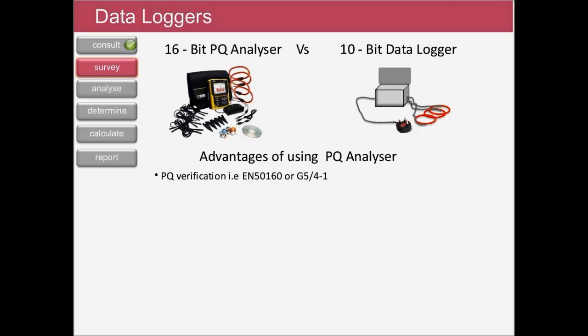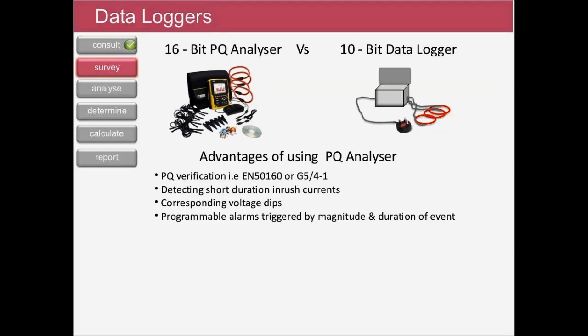Other than the more obvious advantages of being able to verify compliance with power quality standards, the power quality analyzer will detect short duration inrush currents and the voltage dips which are often associated with these events. Bespoke alarms can also be programmed into the analyzer to capture these and other more complex characteristics.